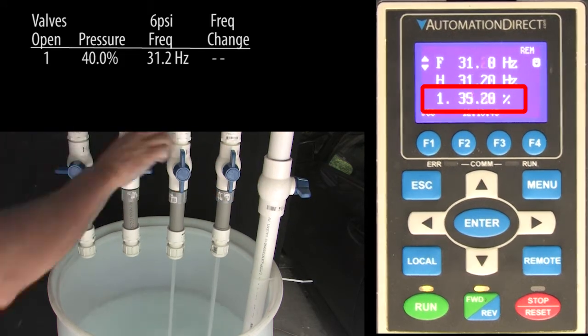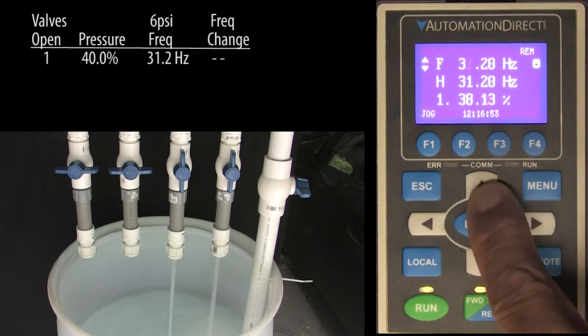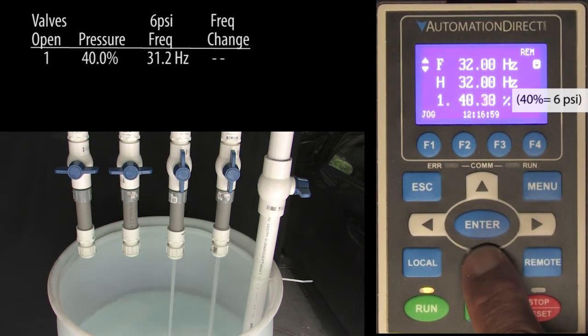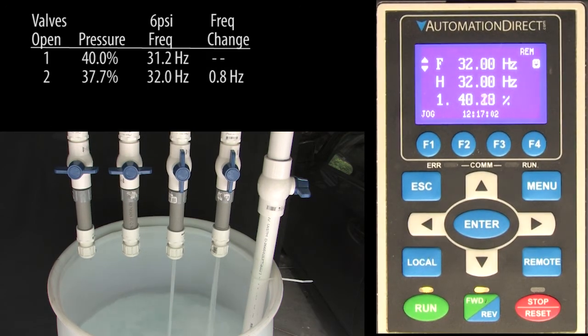If we open the second valve, we see the pressure drop to this. So we increase the drive frequency to get our 6 psi back and add that to the chart. Let's also add how much we had to change the frequency to get our pressure back.